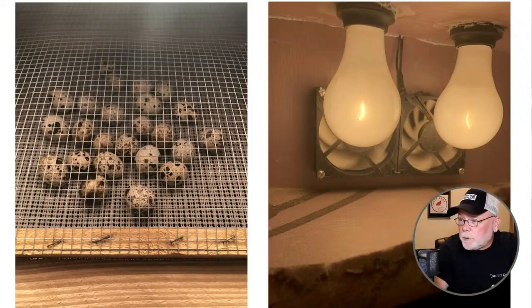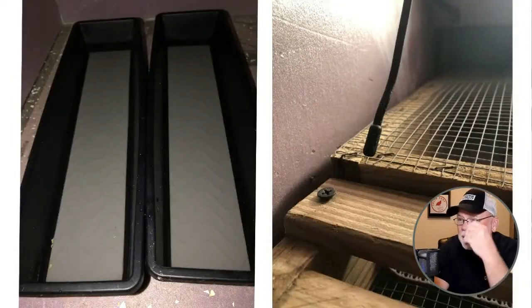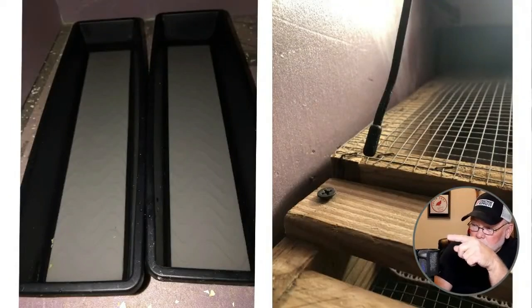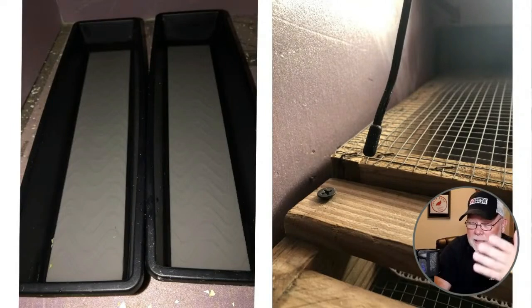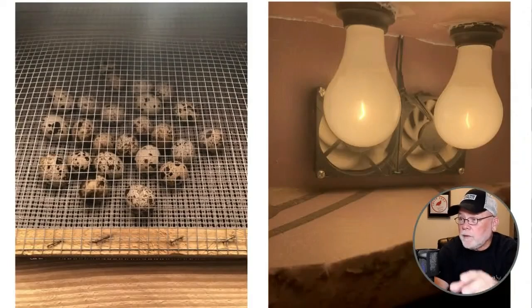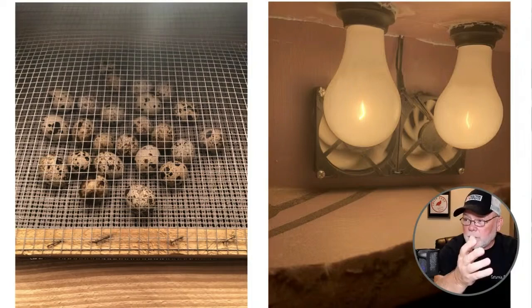I didn't get a shot of it, but behind those fans is a channel on the outside of the incubator, on the back side. It's the forced air channel, and at the bottom of the incubator is where the cutout is. Let me go back to that shot. You can't see it in this picture, but right behind those two water trays there's a little cutout on the back of the incubator, and on the back side of that is a forced air channel that goes up to these fans. That's where it draws the air up, from the bottom of the incubator, through the forced air channel, and then blows it out across the heating elements, which in turn warms the air and keeps it circulating.